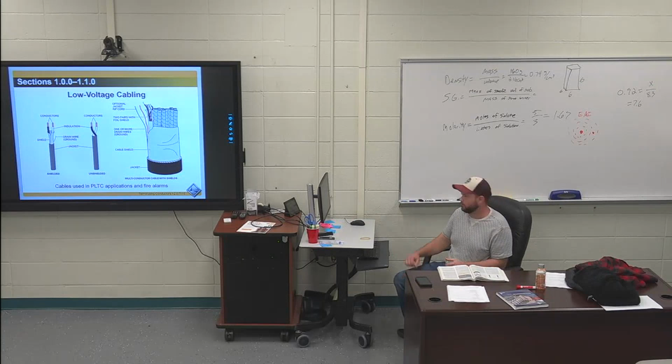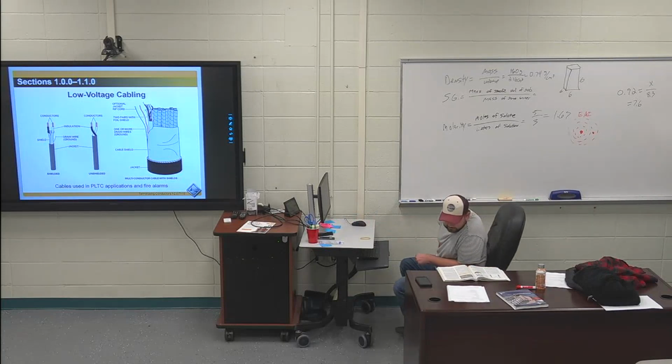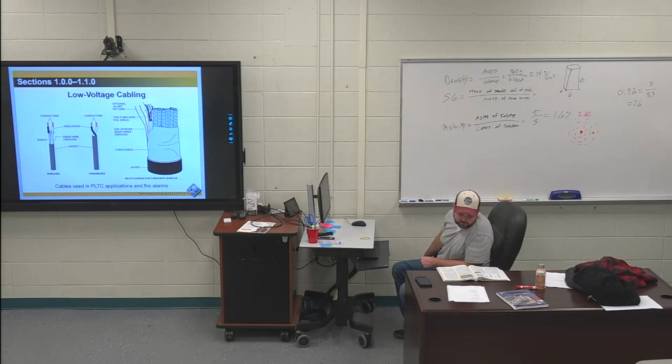Unshielded twisted pair cable. It might be good to know, a lot of times they'll call this UTP, unshielded twisted pair. In the top left of page 3, that second sentence is highlighted. They're currently available as category 3, transmission rates up to 16 megahertz, 4 up to 20 megahertz, category 5 and 5E up to 100 megahertz, 6 and 6A is 250 and 500 megahertz. You want to key in on that category 5. Category 5 or 5E Ethernet cable can handle 100 megahertz.